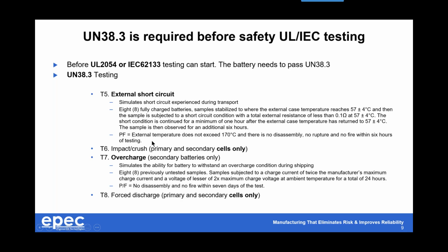And especially the pass-fail criteria, the external temperature cannot exceed 170 degrees C. With us using electronic safeties on the majority of our medical batteries, we never exceed this 57. It just instantly opens and life is good, stays open for as long as we need. And they look for another 6 additional hours and just make sure that indeed the safety's kicked in and they stayed off, and no adverse conditions hours later. So a fairly simple test. But a little further in this presentation, we're going to go over where this 170 degrees C actually does come into play. If you have a low cost medical battery, we'll touch on that a little bit later.